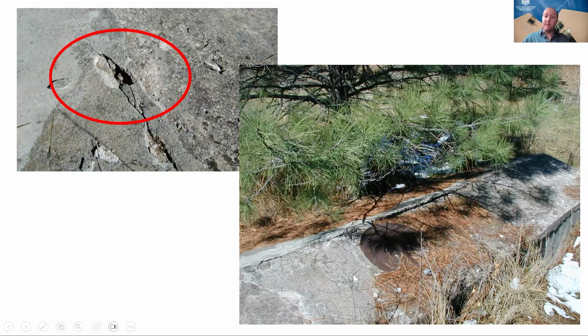But if these are constructed well, they can be really convenient because it's very low energy use, because the water is flowing. You don't need to pump it up like you would with a well. And if you can keep it categorized as groundwater, there are pretty minimal treatment requirements, depending on the quality of that water, of course. Where I worked in Bozeman, Montana, one of our sources was a spring, and we had a spring box that was well constructed, so it was protected from the outside air and any surface water.